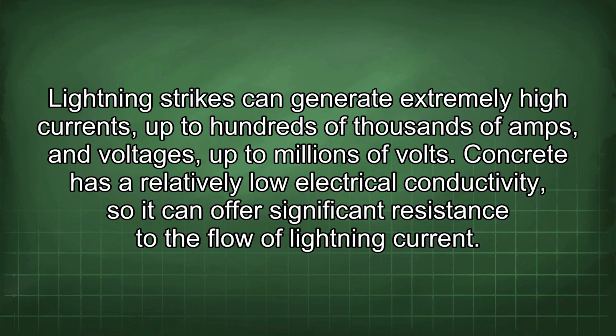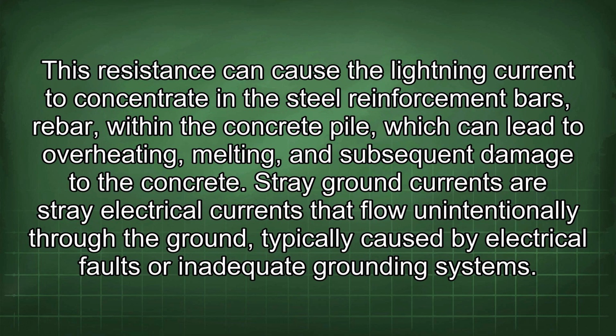Lightning strikes can generate extremely high currents, up to hundreds of thousands of amps, and voltages up to millions of volts. Concrete has a relatively low electrical conductivity, so it can offer significant resistance to the flow of lightning current. This resistance can cause the lightning current to concentrate in the steel reinforcement bars, rebar, within the concrete pile, which can lead to overheating, melting, and subsequent damage to the concrete.